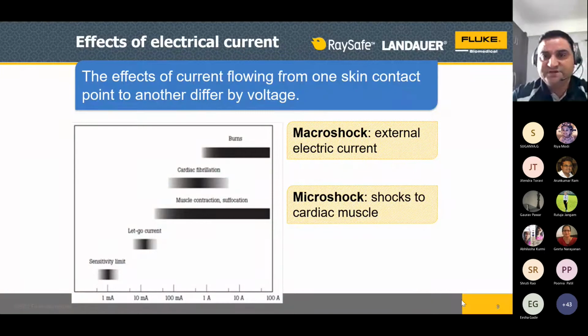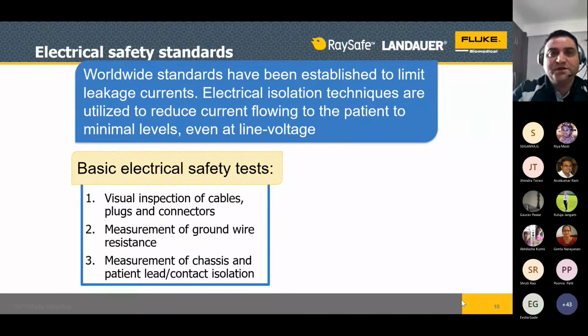If equipment fails, it has to fail in the biomedical department, not in the ICU, not in the OT. Please remember this. This is the job of a biomedical engineer. So worldwide standards have been established to limit leakage currents. This is the main agenda why IEC was framed. They wanted to ensure that minimum leakages are there, and those are within the permissible limits.